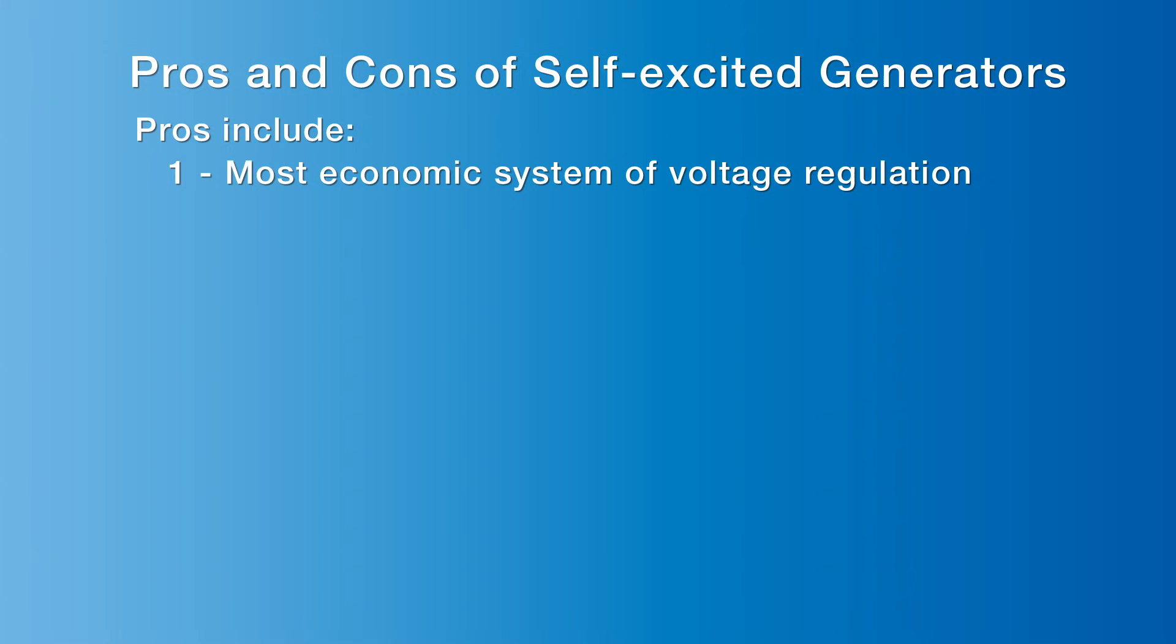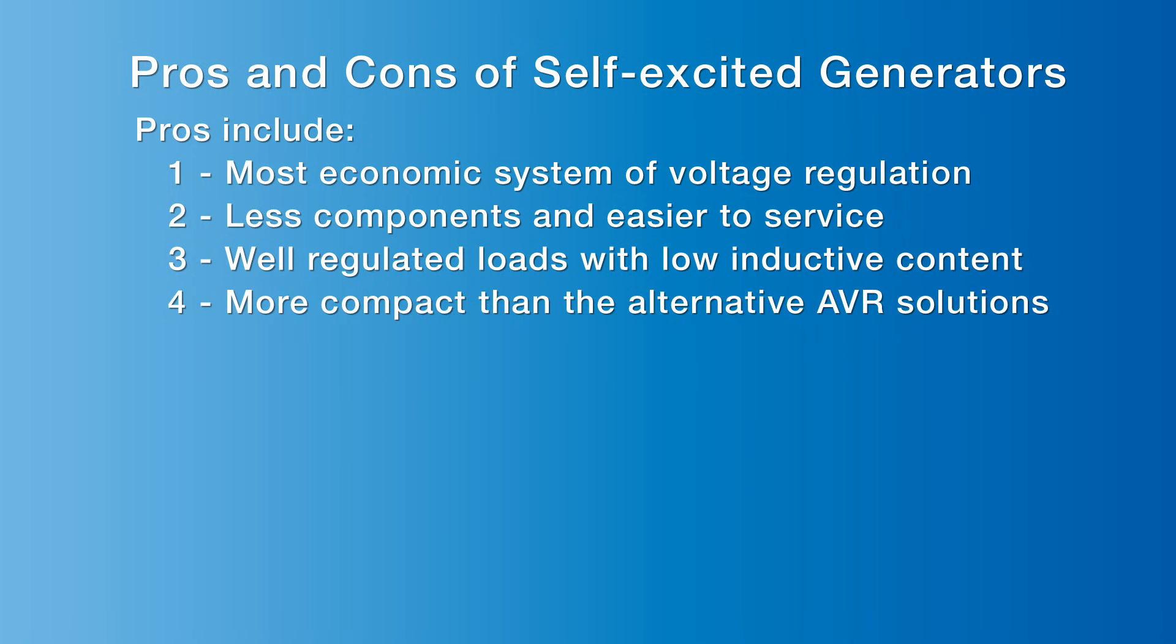There are pros and cons with a self-excited system. Pros include most economic system of voltage regulation, less components and easier to service, well-regulated loads with low inductive content, and more compact than the alternative AVR solutions.